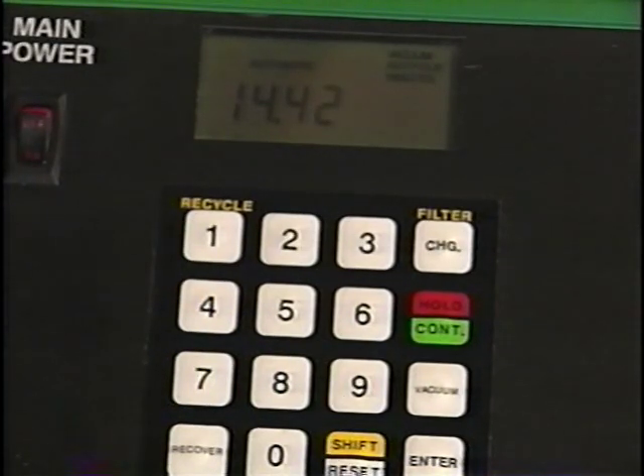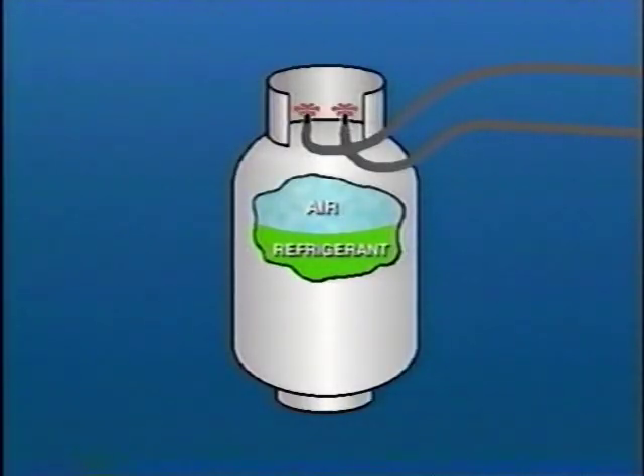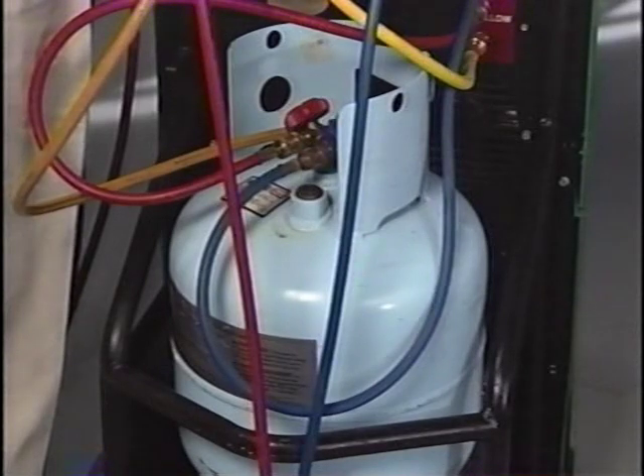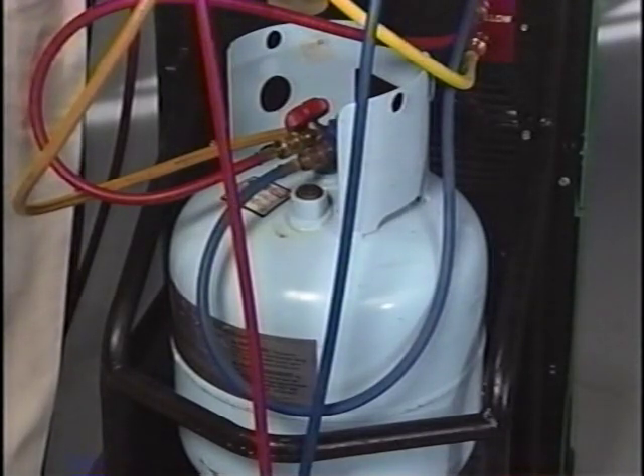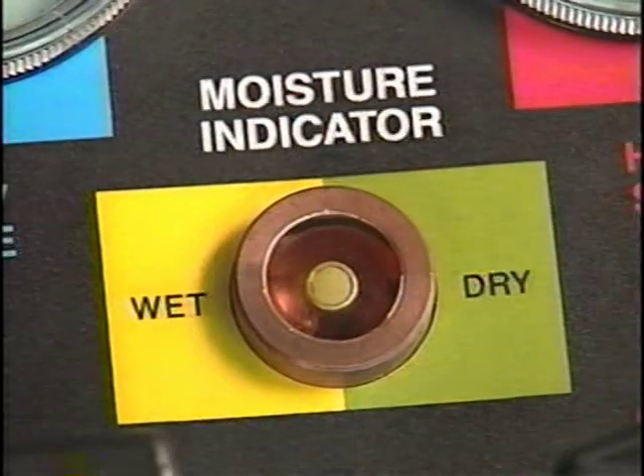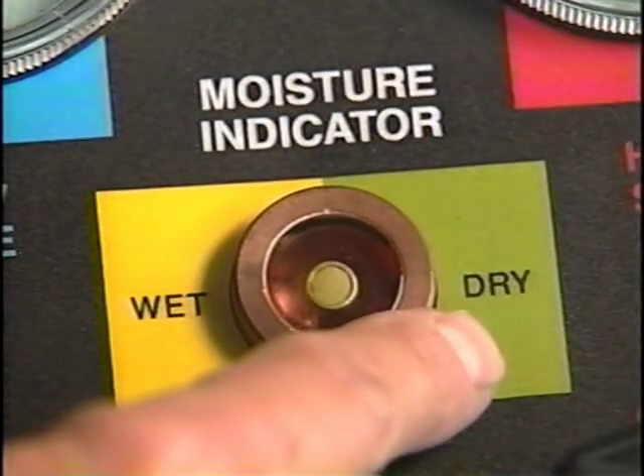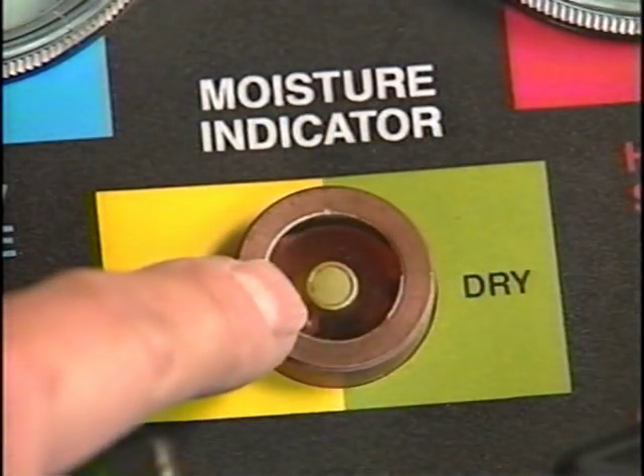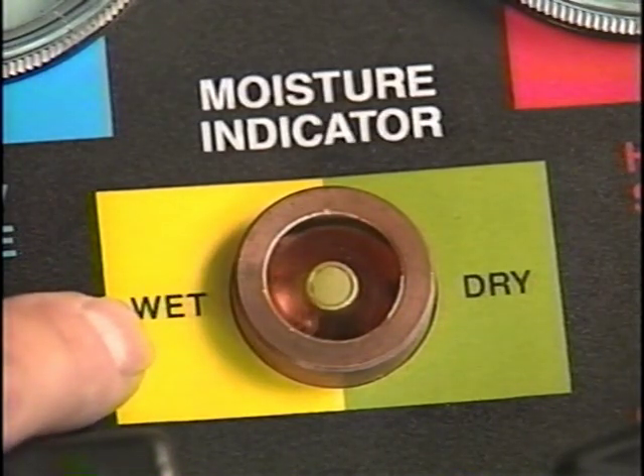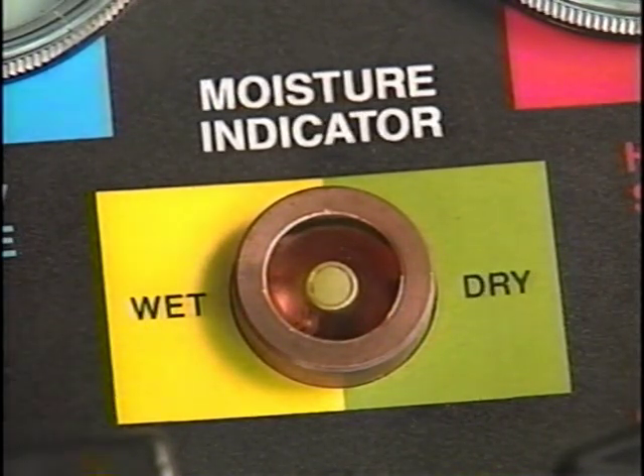During the evacuation process, the ACR4 automatically recycles the refrigerant through the filter dryer. It also purges air and any other non-condensable gases from the system. You may hear the sound of pressure releasing as the system vents. Tank pressure also increases during evacuation, allowing more efficient charging of the vehicle. Remember, the moisture indicator on the unit control panel must be green. This verifies the moisture content of the refrigerant is within specifications. The yellow indicator indicates a wet condition and requires that the filter dryer cartridge should be changed.